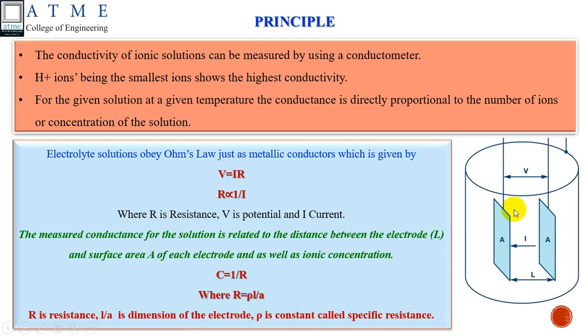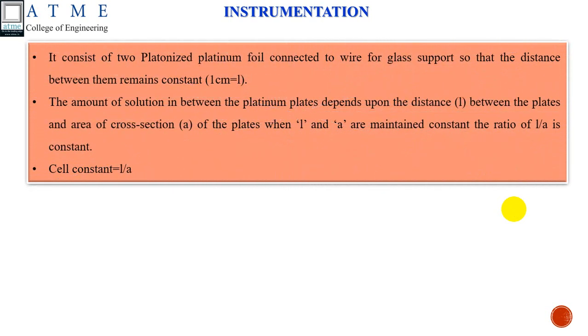If L and A are maintained constant — for example, electrodes kept one centimeter apart — we call it the cell constant. The conductivity cell has a cell constant. If we move on to the instrumentation part, it mainly consists of a conductivity cell with two platinum foils supported with glass for mechanical support, kept at a distance of one centimeter apart. The conductance depends on the ions present between the two platinum foils. With L and A kept constant, the cell constant K = L/A.